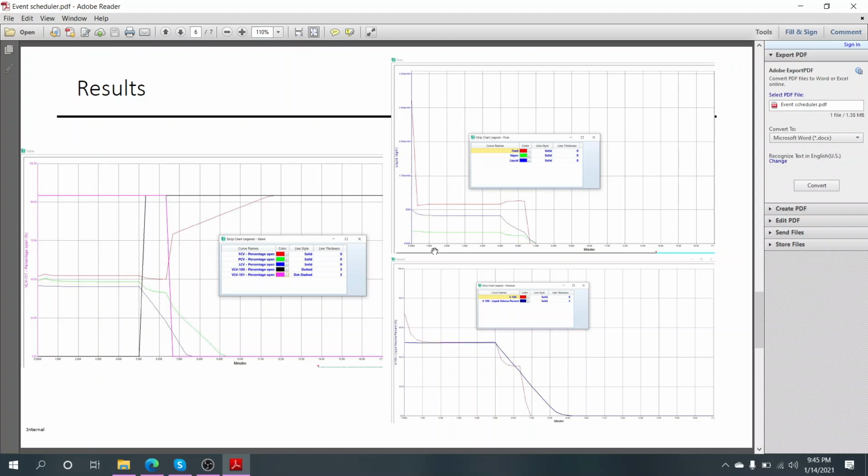Level is shown here, the blue one. So it will have a decrease in the level. When the level drops to 30%, which is somewhere around 6 minutes something, VLV 101 will be closed. So this VLV 101, the purple one, which color is this? Pink. Sorry. So this pink, at around 6 to 7 minutes where the level drops to 30%, will then close automatically to shut off the liquid flow rate, or the feed stream coming into the vessel. So that's basically what is happening.